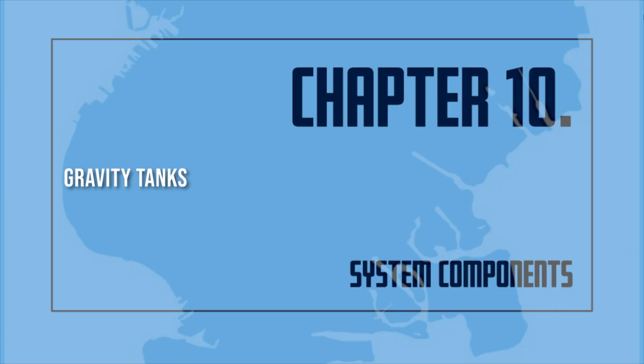It does not depend on the operation of mechanical equipment to supply the sprinkler system. Automatic fill pumps supply the water to most gravity tanks. The pumps fill the tank at a rate of 65 gallons per minute or more. The floats turn on the fill pump when the water in the tank is too low. The floats shut off the pump when the desired water level is reached. The floats make sure the gravity tank always has the right amount of water to supply the sprinkler system.